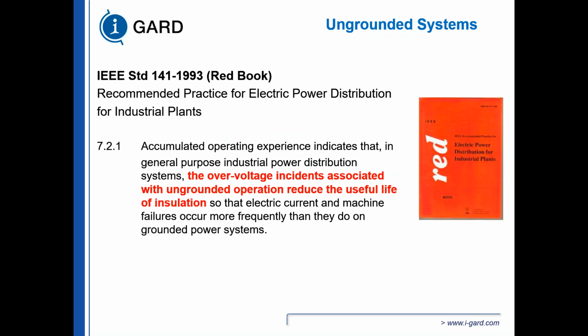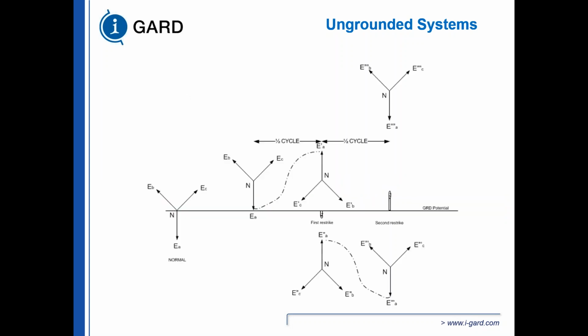The Red Book states that overvoltage incidents associated with ungrounded operation reduce the useful life of insulation. So it is possible for you to damage your cable due to these sputtering arcing faults, where you can have puncture holes going through your insulation on your cabling system, because the weakest link in your system is going to fail. So you can see here how a system becomes 6 to 8 times the potential with respect to ground.